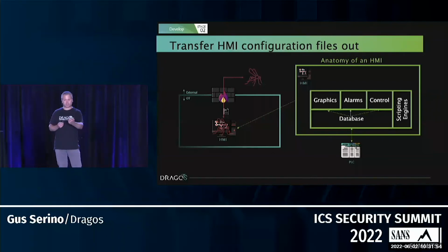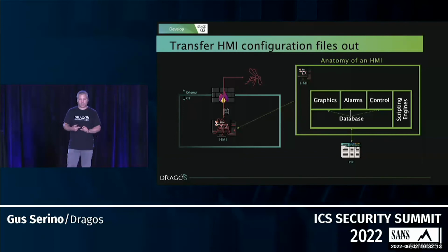There are tags built into those graphics, alarms, and so on. Within that HMI database are things like alarms, set points, engineering units, and other data. But one really important thing in there is the IO address for the memory location in the PLC where that piece of data lives. That's the crux of why just having HMI access is enough in a lot of cases.